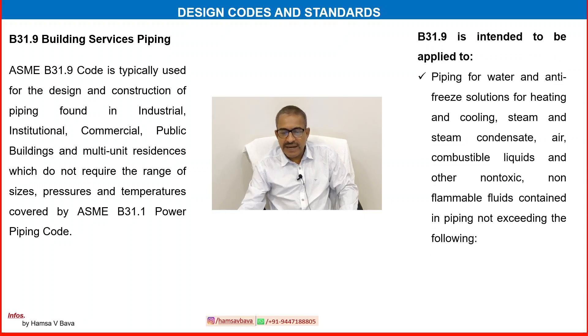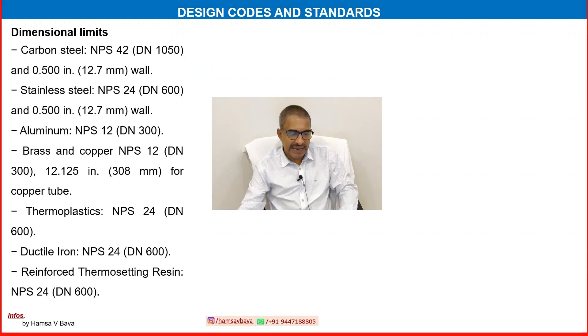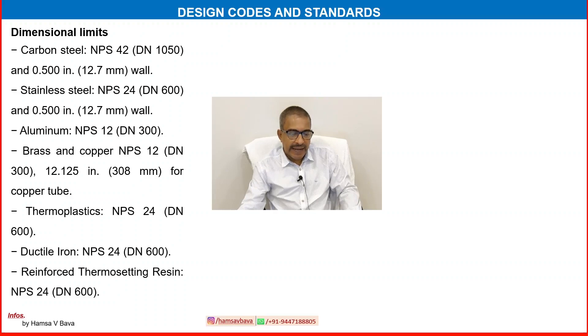This code is intended to be applied to piping for water and anti-freeze solution for heating and cooling, steam and steam condensate, air, combustible liquids and other non-toxic, non-flammable fluids contained in piping not exceeding the following. It is mainly used in building services. Materials include carbon steel, stainless steel, aluminium, brass and copper, thermoplastic, ductile iron, and reinforced thermosetting resins.